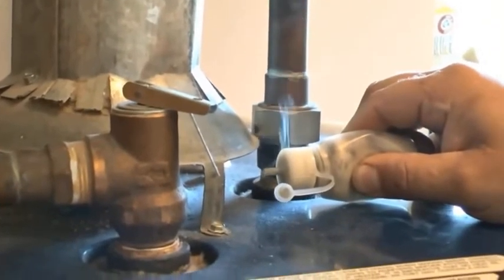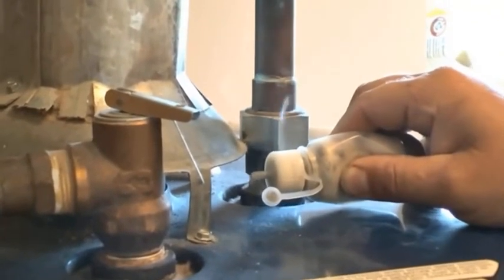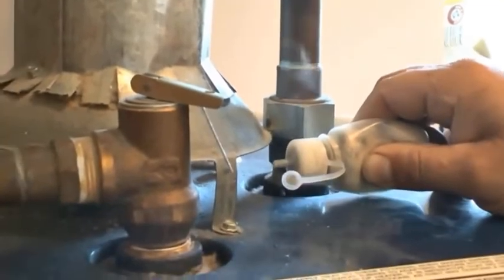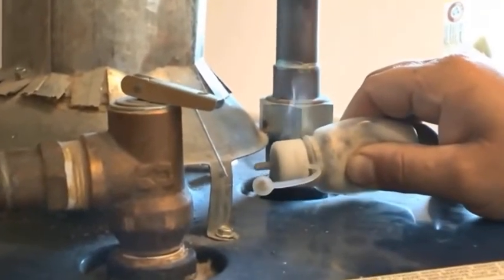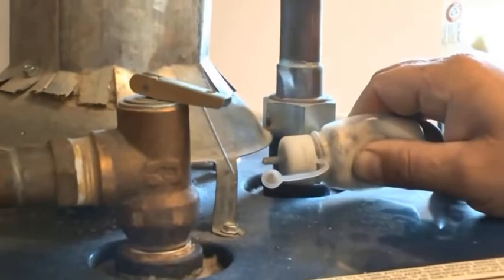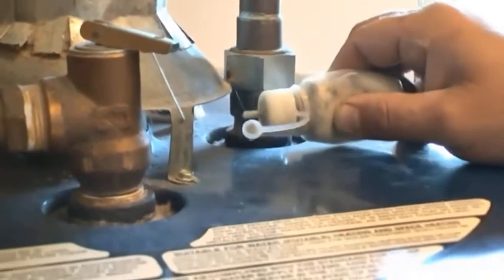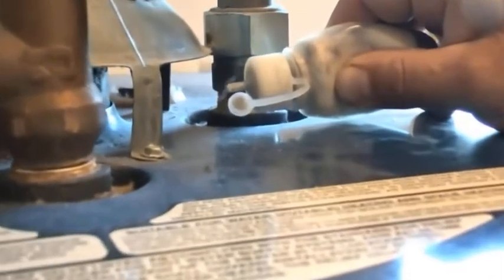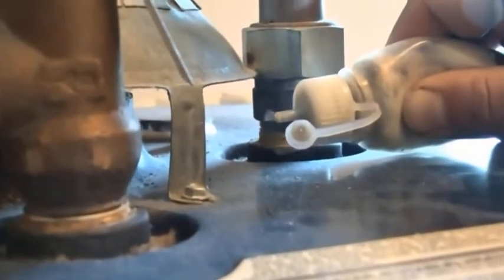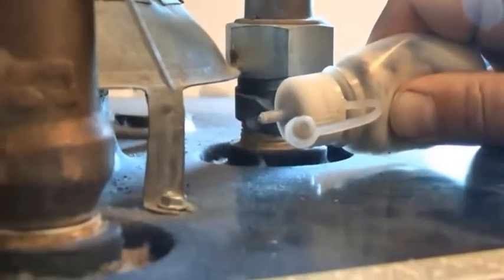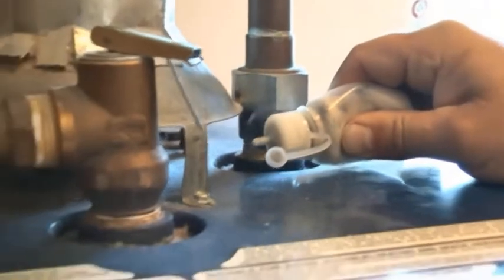Okay, we're still backdrafting. We're starting to get a little bit of draft, but we do still have some backdrafting effect here. Basically, we're past a minute and we still have backdrafting. This fails worst case combustion air zone test.